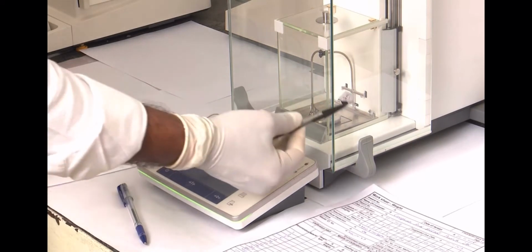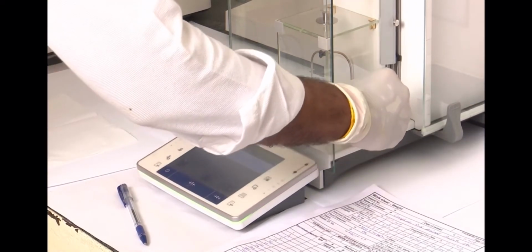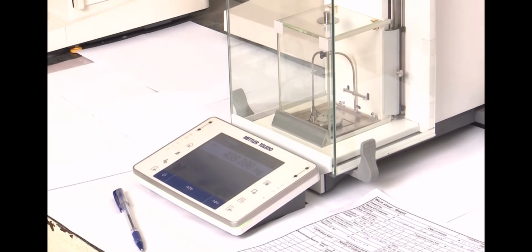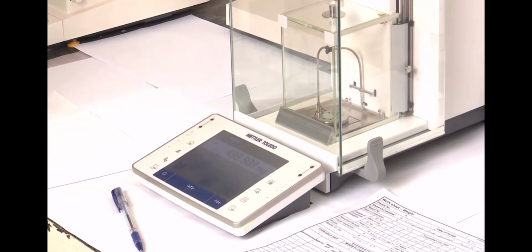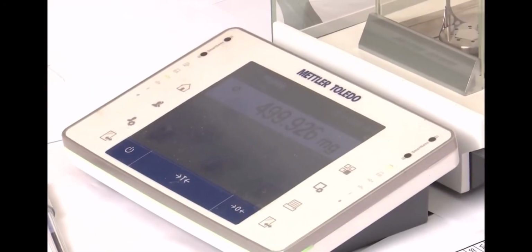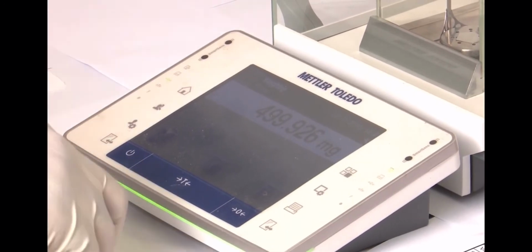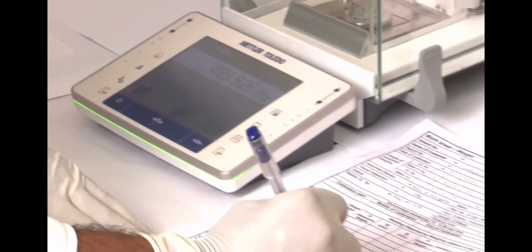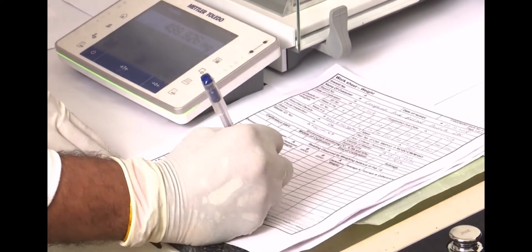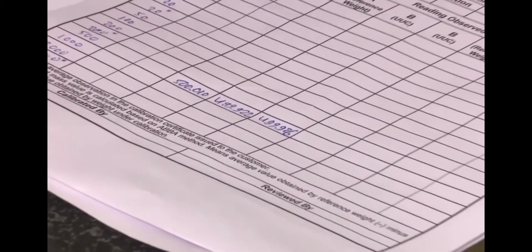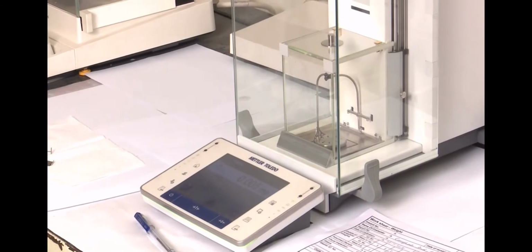Put again the weight under calibration on the center of the pan of the balance. Close the door, allow it to stabilize and note down the reading shown by weighing balance as B. Take out the weight under calibration and allow the balance to stabilize at 0.